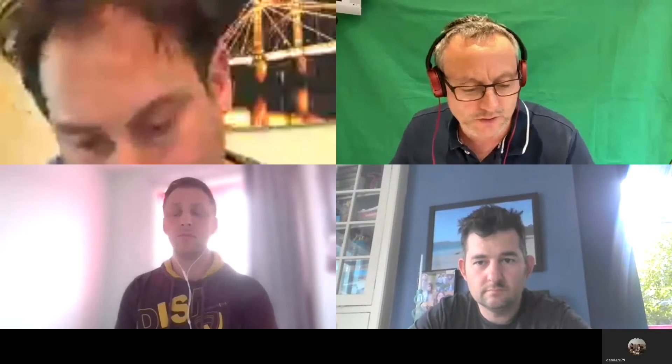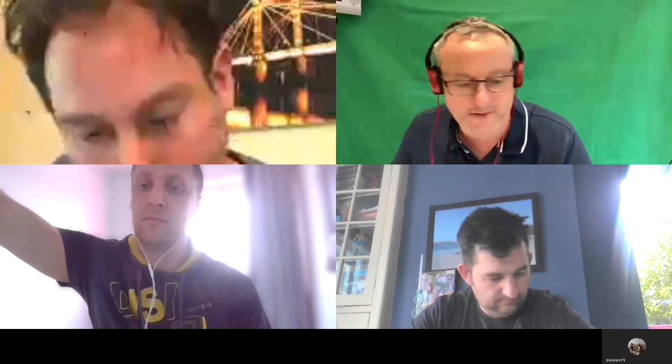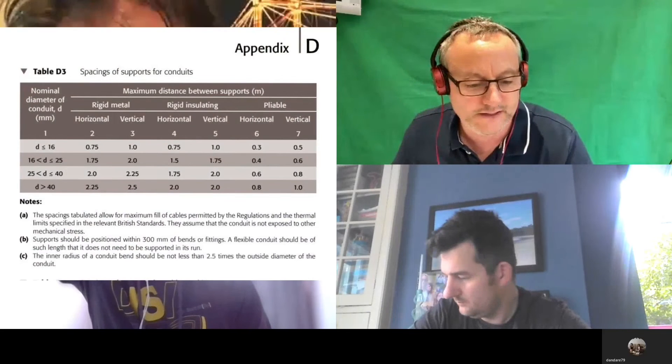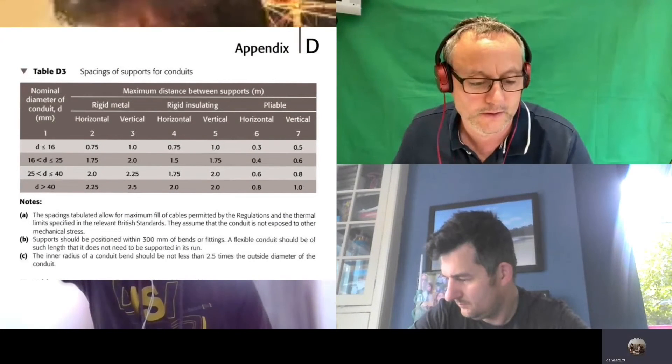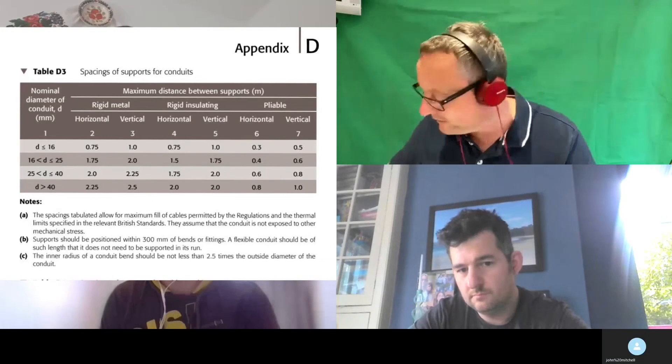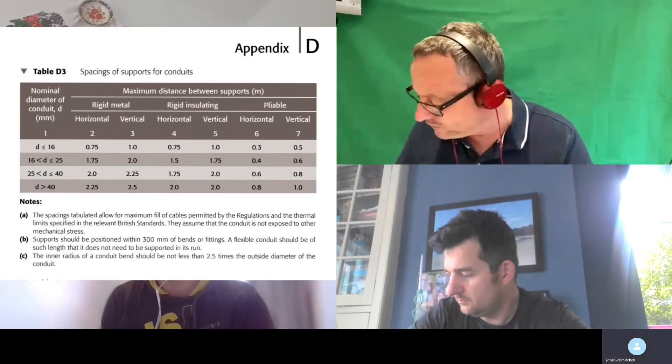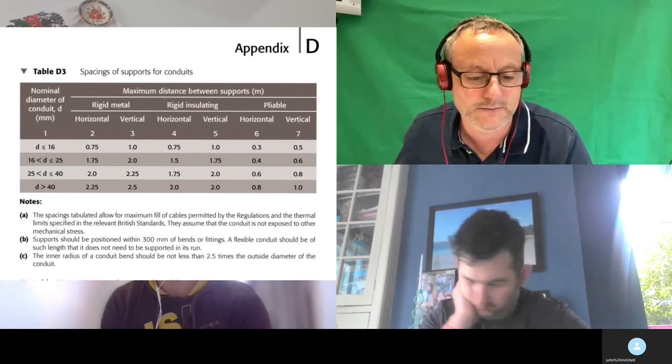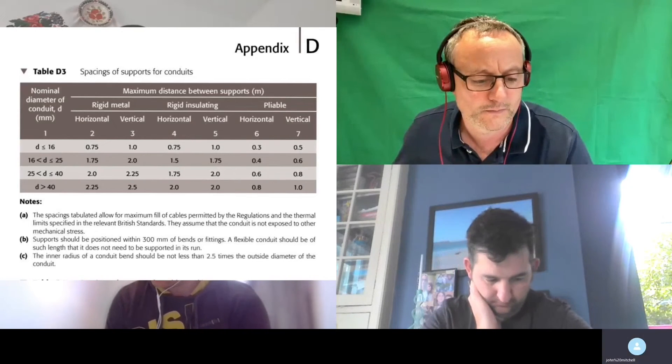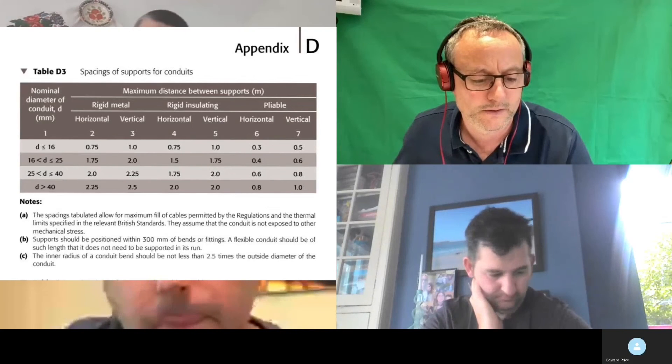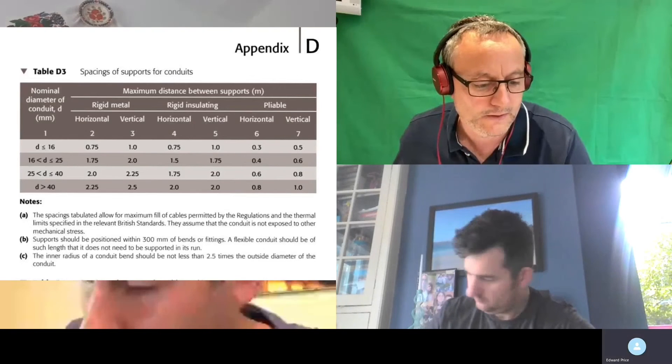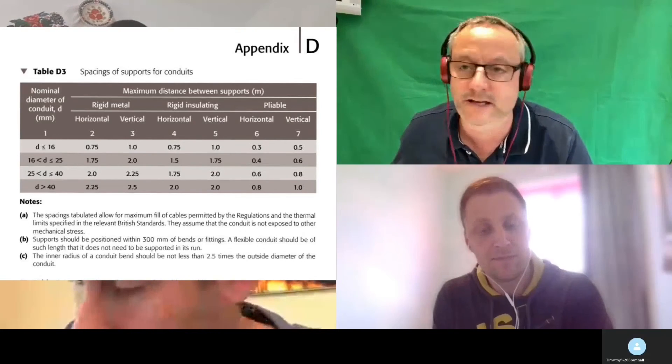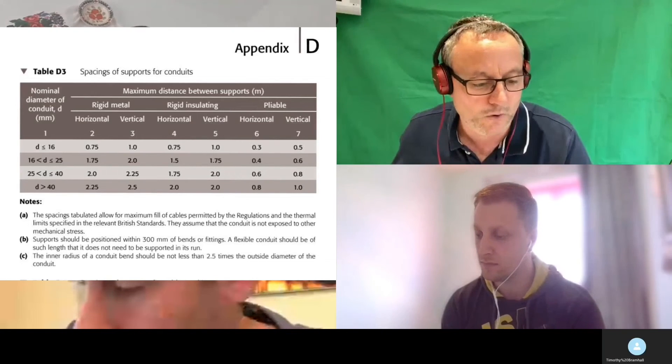We're done Dan. You want to go first? If I had metal conduit and it was 16mm diameter, what is horizontal and vertical fixings, maximum distance between supports please? 0.75 and 1.0. One meter, well done. If we go next for John, if I had a 20mm conduit that's metal, vertical and horizontal, maximum distance between supports? Horizontal 1.75 and vertical two meters. Brilliant. And Ed, if you jump down to 25mm metal conduit? The same, 1.75 and two meters. Yeah, both of those encompassed in the same line.